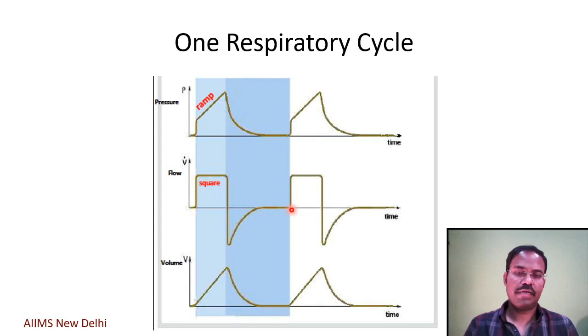Now there are three different variables. If you analyze each complex of the waveform, you will realize that the ventilation starts with a trigger. Point A suggests that this is the trigger. It can be a time-based ventilation, which is a time-triggered ventilation, or a patient can trigger his own. This can again be a flow trigger or a pressure trigger, depending on what the ventilator senses.